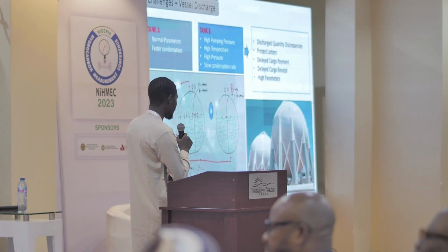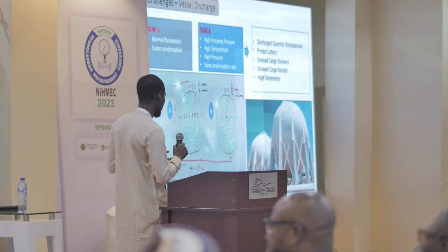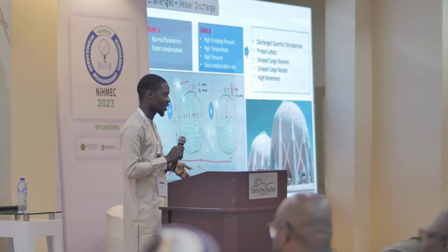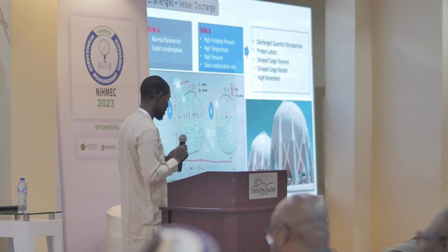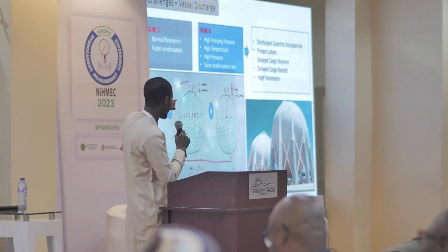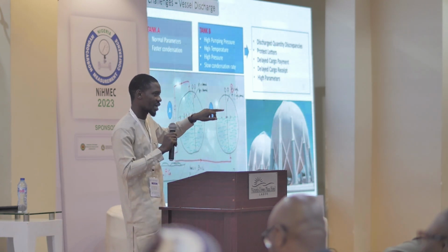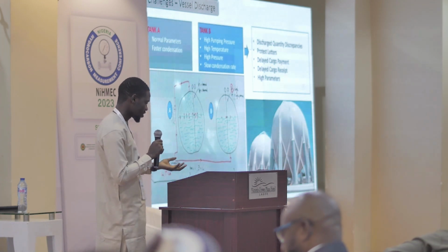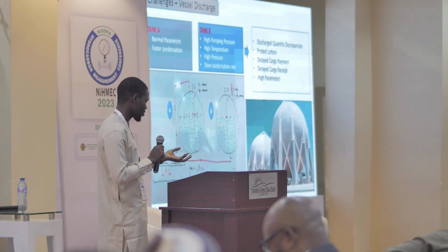The main reason is this: assume you're receiving a refrigerated LPG cargo at -2 degrees, and you have a vapor phase in your tank at around 30-something degrees. While you're pushing this very cold, chilled product up, the vapor will find it difficult to shift immediately from 30 degrees to, say, 3 or 4 degrees. It definitely needs time, and that time you don't have, because you have a vessel waiting and demurrage is coming. You want it to move.